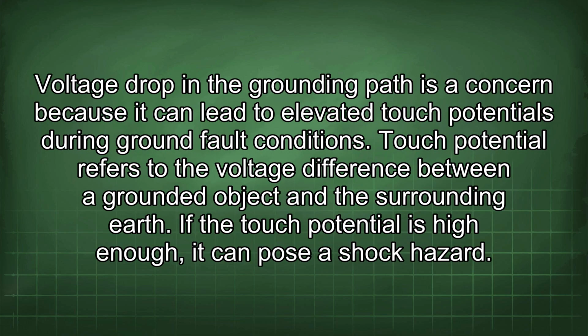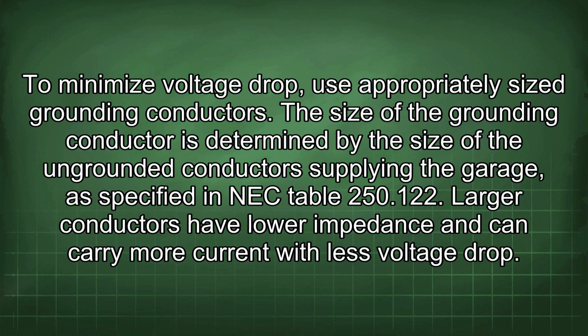Voltage drop in the grounding path is a concern because it can lead to elevated touch potentials during ground fault conditions. Touch potential refers to the voltage difference between a grounded object and the surrounding earth. If the touch potential is high enough, it can pose a shock hazard. To minimize voltage drop, use appropriately sized grounding conductors.